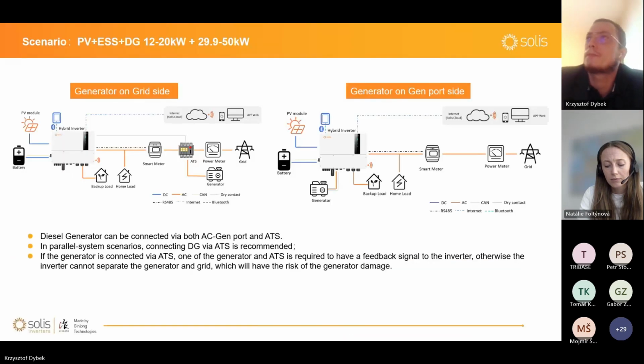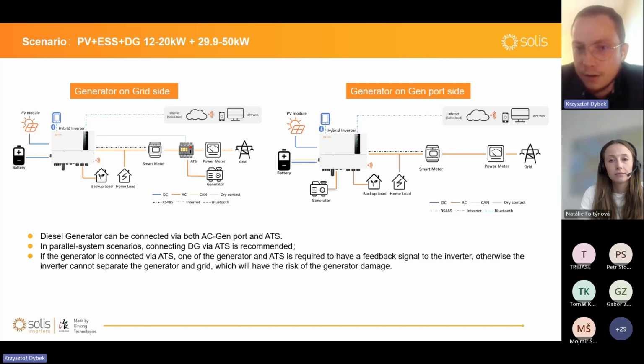Yeah, and those are typical scenarios when you can use this bigger commercial 12 up to 50 kilowatt inverter. So the generator starts to work when, during grid loss, the battery is drained until generator start SOC. This is how it's called. Then the inverter enables the generator. The generator has a task to charge the load and battery until the battery hits generator exit SOC. If the generator fails to start, the battery will be discharged until over discharge SOC as normal. So the logic of this ATS control, as we see it here: to start the generator, relay pull in, dry contact short circuit. To stop the generator, relay release, and dry contact open circuit.